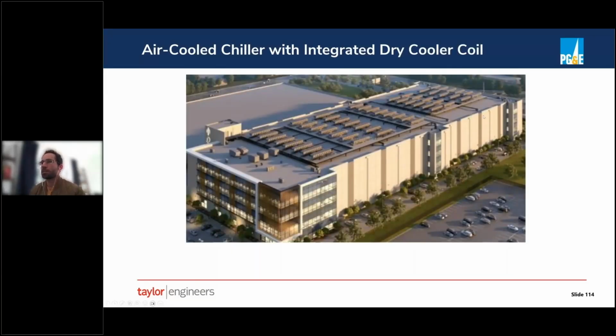Water usage is becoming a more and more important consideration in data center design. And so we see a lot of owners going for strategies that minimize water usage. In a lot of cases, it's also just a means of simplifying things. So we see a lot of colo facilities where instead of having a water-cooled chilled water plant, they'll instead have an air-cooled chilled water plant. And one way to eke out some additional efficiency from that design is to use an integrated dry cooler.